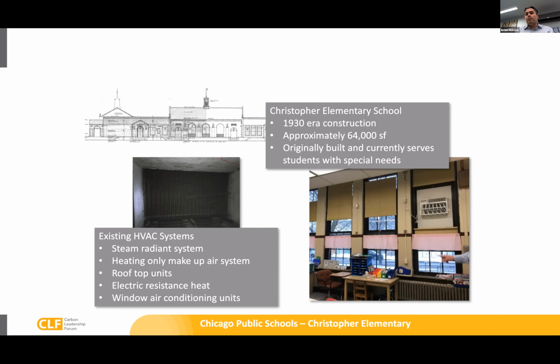The building has a steam radiant system that was original to the building. The boilers had been replaced in the 90s, but the vast majority of the steam system was intact, and this included the makeup air handling unit, which was original, so it was a 90-year-old air handler still in operation.